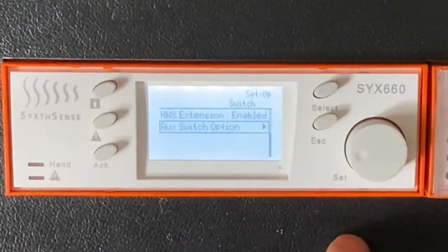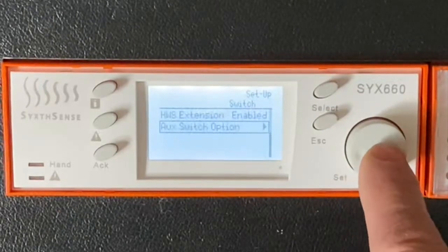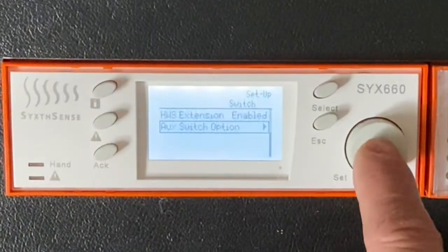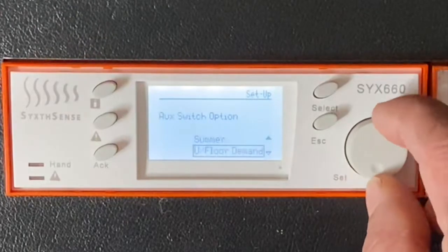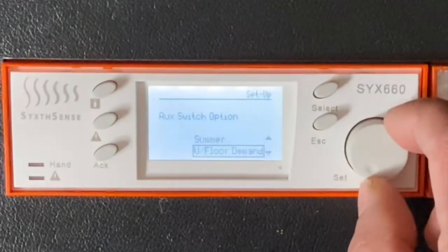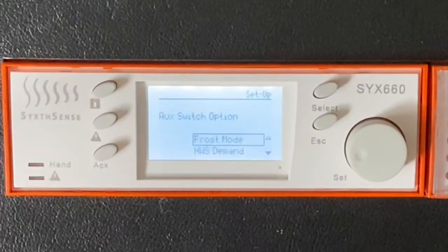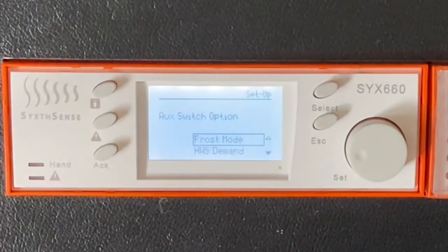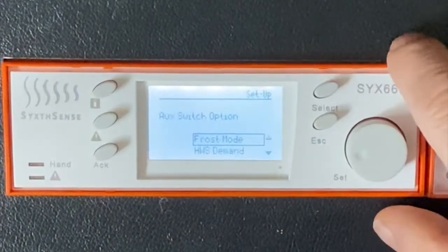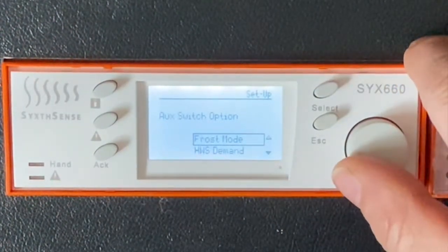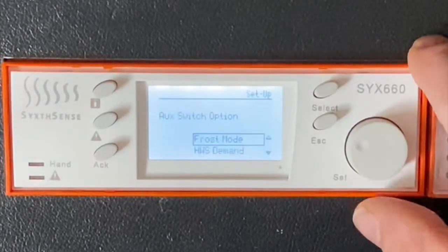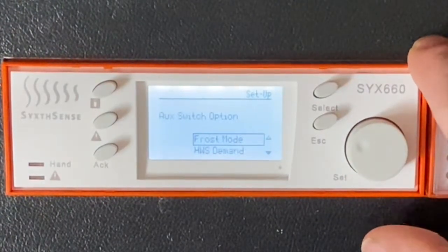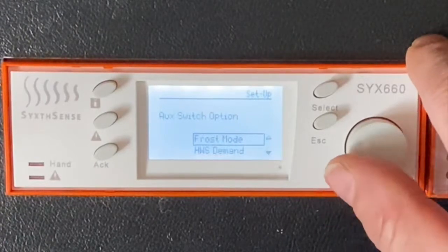The next option is auxiliary switch option. We press the wheel on auxiliary switch option, and we can turn the wheel then and select the mode of use for that auxiliary input. The auxiliary input is on terminals 29 and 30, and if we have a volt-free contact connected onto those 2 terminals, we can choose what feature or override function it has on the controller. The default mode is frost mode, so we would use that typically for a holiday switch.